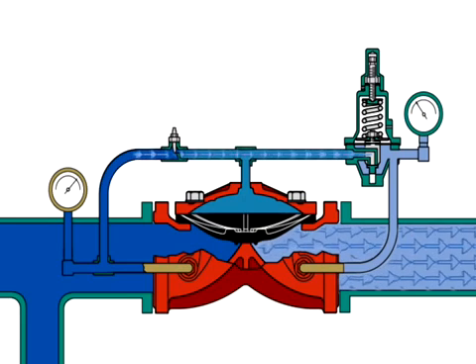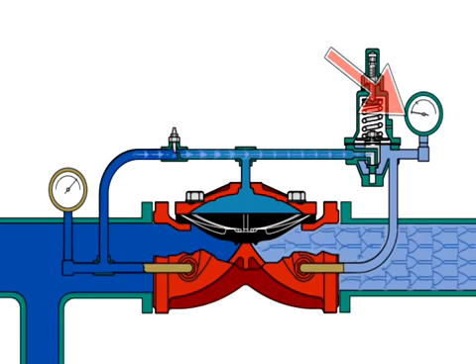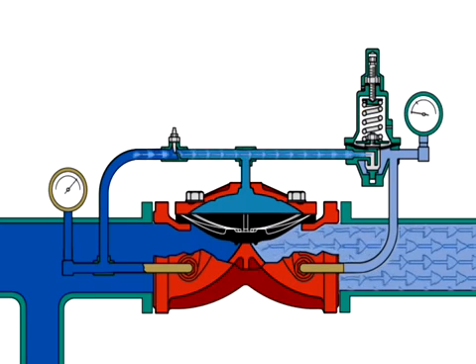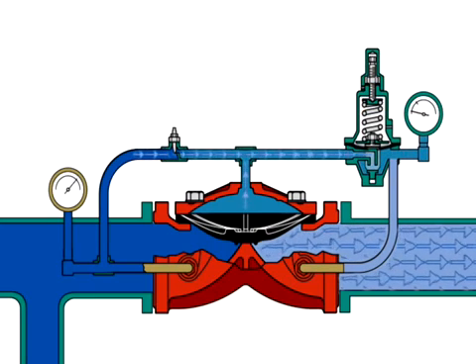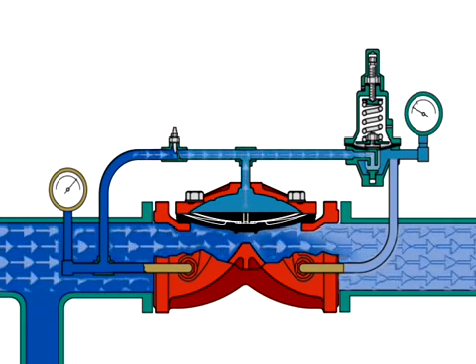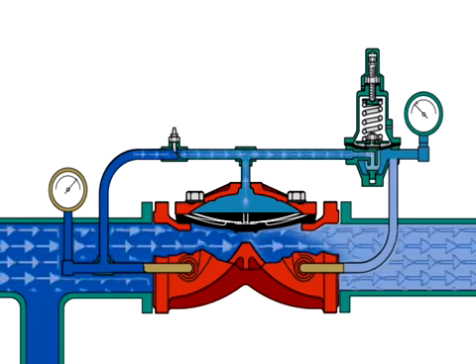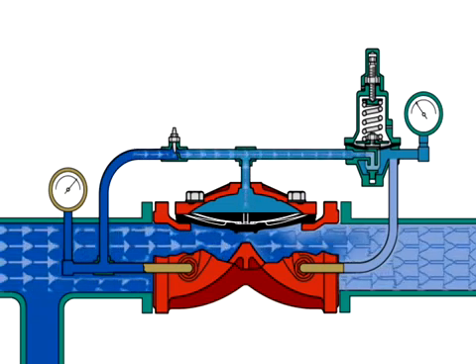When there is a flow demand downstream, outlet pressure drops below the set pressure. The pilot valve seat opens to relieve pressure from the diaphragm chamber, allowing the PRV-1 diaphragm to lift, opening the valve.